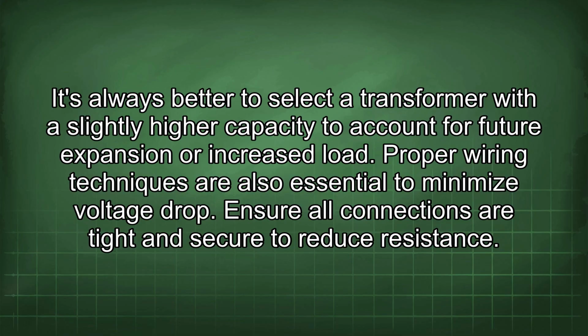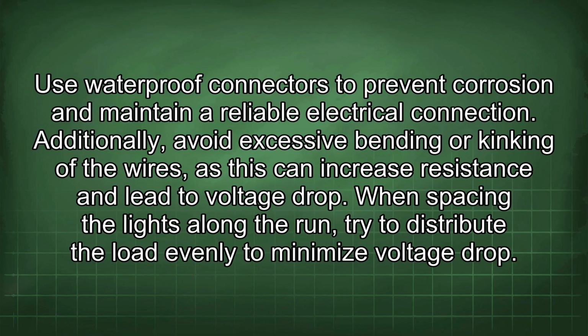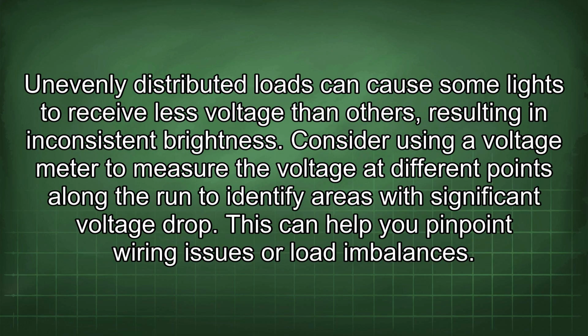Proper wiring techniques are also essential to minimize voltage drop. Ensure all connections are tight and secure to reduce resistance. Use waterproof connectors to prevent corrosion and maintain a reliable electrical connection. Additionally, avoid excessive bending or kinking of the wires, as this can increase resistance and lead to voltage drop. When spacing the lights along the run, try to distribute the load evenly to minimize voltage drop. Unevenly distributed loads can cause some lights to receive less voltage than others, resulting in inconsistent brightness.